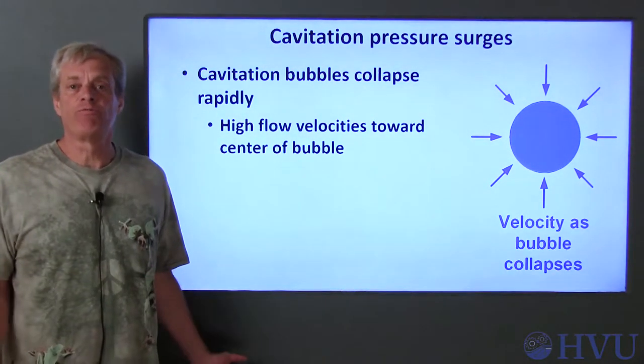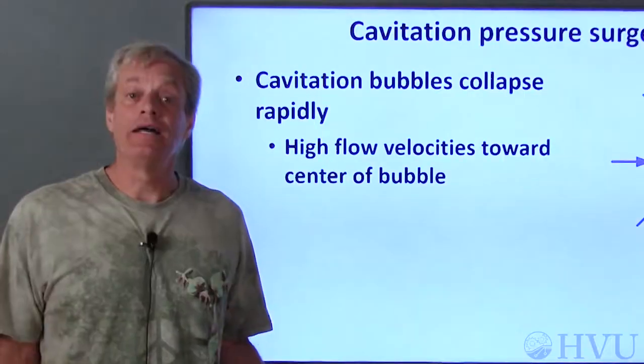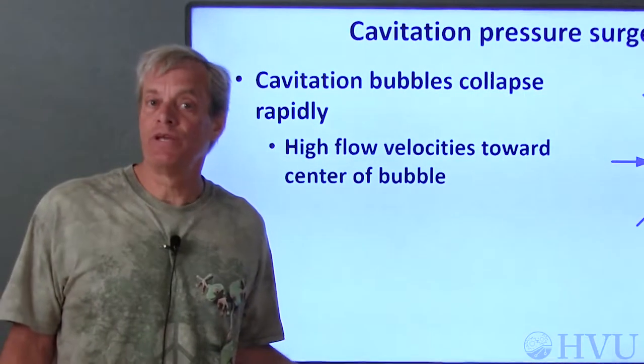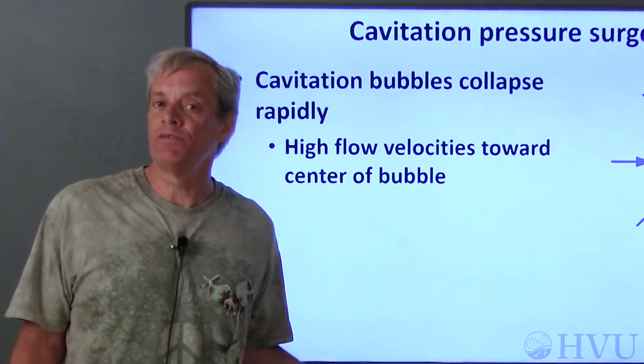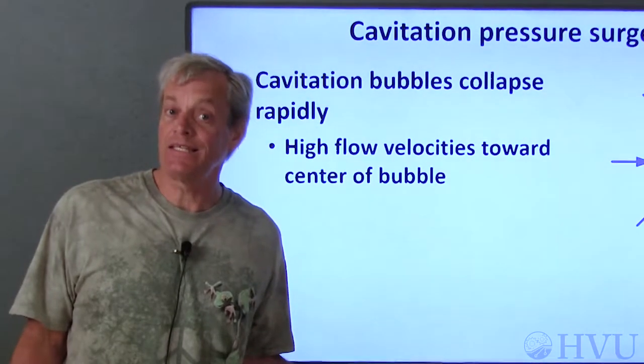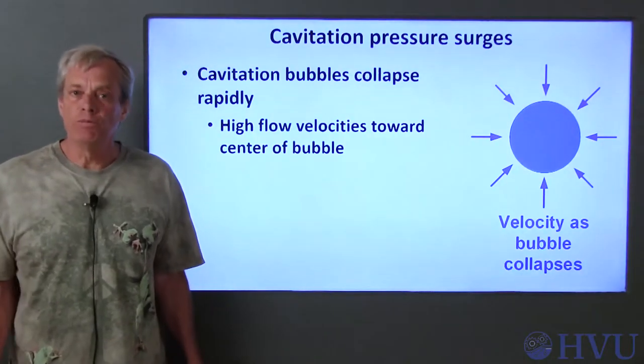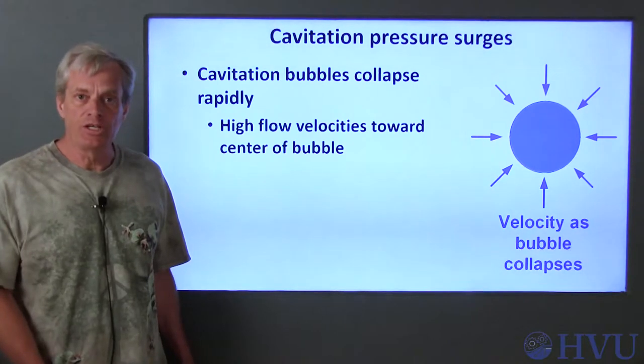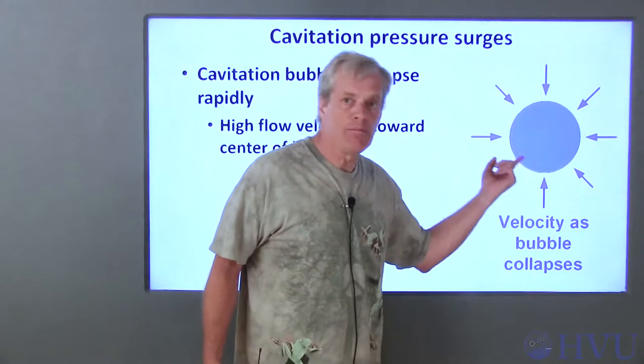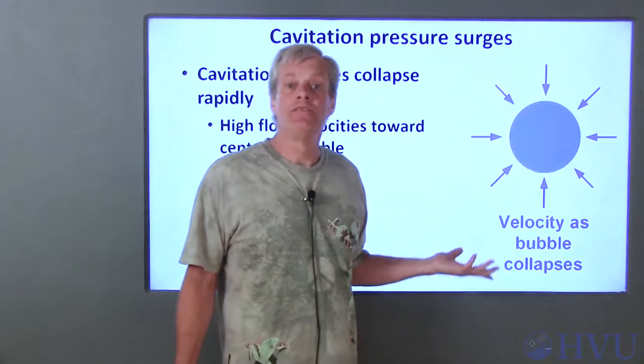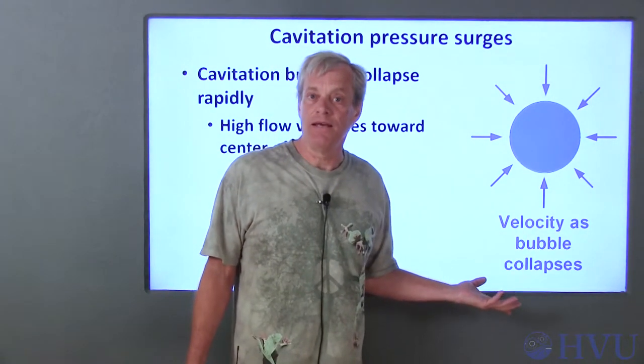Cavitation bubbles form when the fluid enters a low pressure zone. Unlike bubbles created by heat input, the only reason the cavitation bubbles exist is the low pressure surrounding them. So if the bubble moves into a higher pressure region, there's nothing inside the bubble to resist its collapse. The vapor converts back to fluid almost immediately.